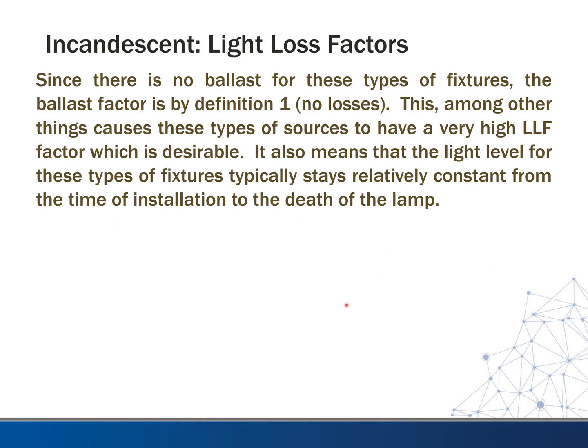If we look at light loss factors, since there is no ballast for these types of fixtures, the ballast factor is by definition one — that is, no losses. This causes these types of sources to have a fairly high light loss factor, which is desirable. It also means that the light level for these fixtures typically stays relatively constant from the time of installation to the death of the lamp. Typical light loss factor for this luminaire is in the high 90s, around 97% on average.